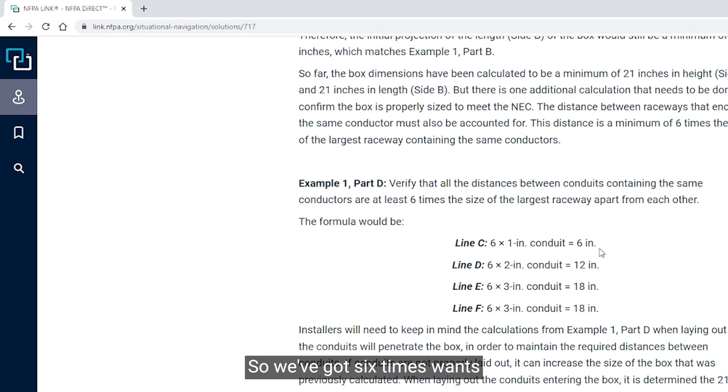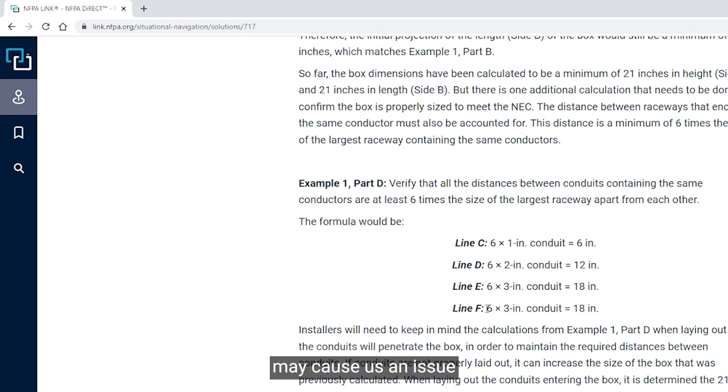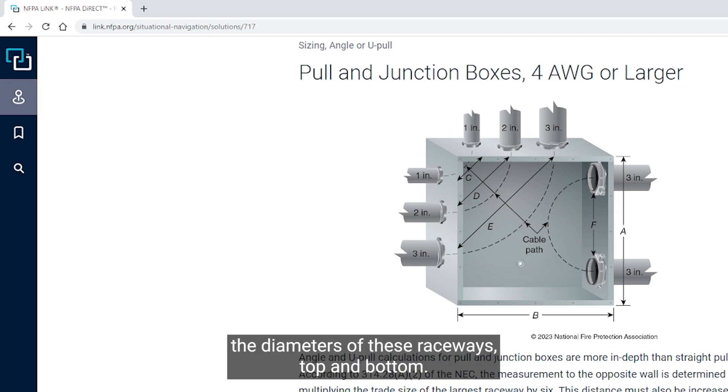So we're going to be looking at line C, line D, line E, and line F, and that is in Example 1, Part D. We're going to have to verify that these are separated far enough. Installers, you will need to keep in mind the calculations from this example when laying out how the conduits will penetrate into the box or enter the box to maintain the required distances between conduits. If conduits are not properly laid out, it can increase the size of the box that was previously calculated. When laying out conduits entering the box, we've got 6 times 1, so 6 inch, 12, and diagonally 18 inches.